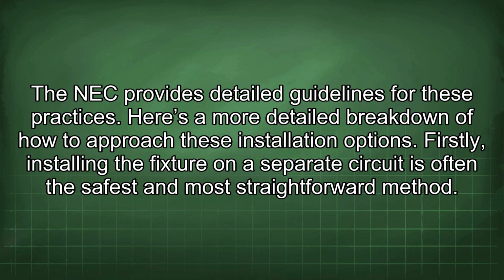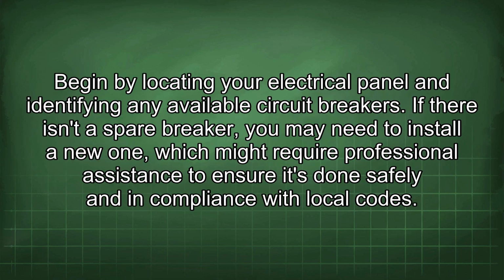Here's a more detailed breakdown of how to approach these installation options. Firstly, installing the fixture on a separate circuit is often the safest and more straightforward method. Begin by locating your electrical panel and identifying any available circuit breakers. If there isn't a spare breaker, you may need to install a new one, which might require professional assistance to ensure it's done safely and in compliance with local codes.